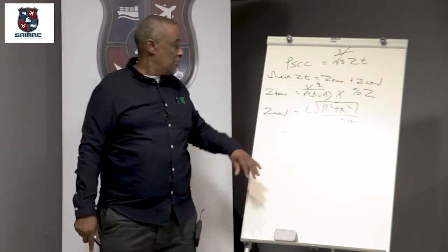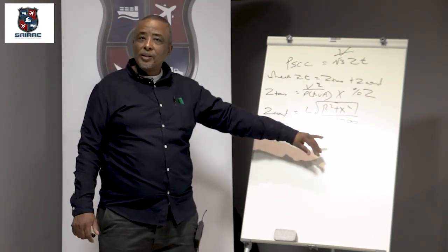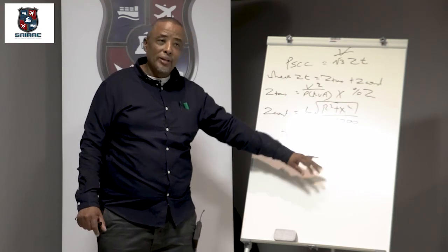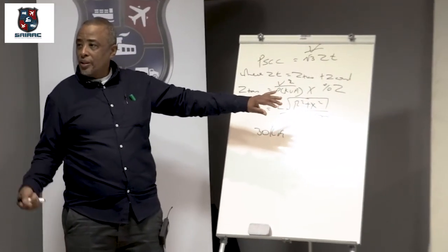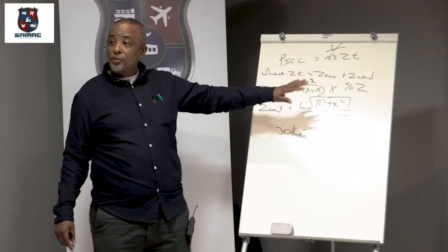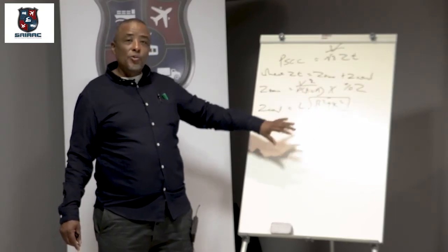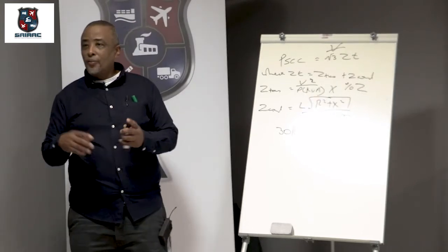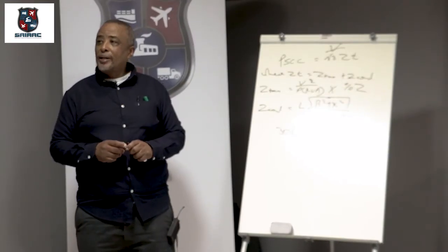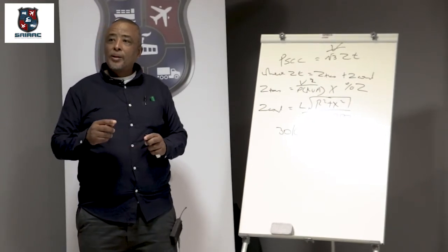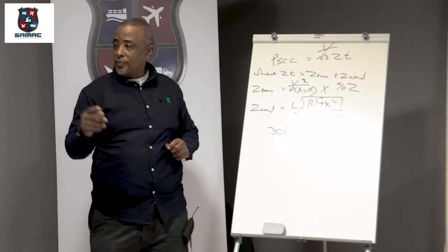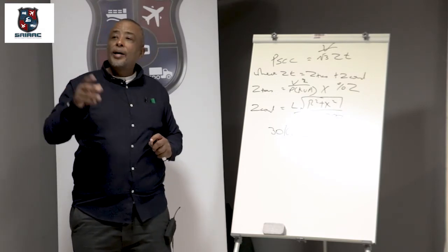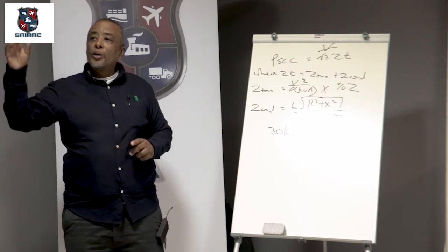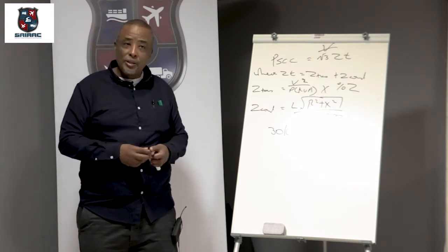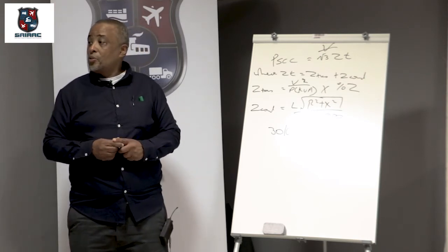Okay, the next dB, I don't need 10 kA. I can go maybe 5 kA. The next dB, 3 kA, and so on. Downstream, you don't need to have such a high protection because it's costly, especially in a factory where there's lots of dBs. So this is where the consultant will work it out. He'll say, okay, I'm going to use CBI, and CBI is guaranteeing me that I will have the necessary protection downstream if I use their circuit breakers, and I could get away with using a less capacity circuit breaker. Okay, it's all about cost. This is what cascaded means.